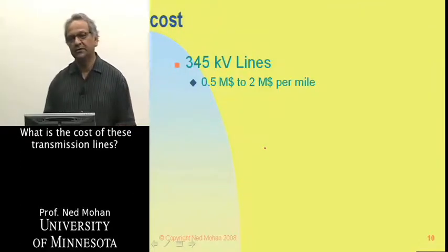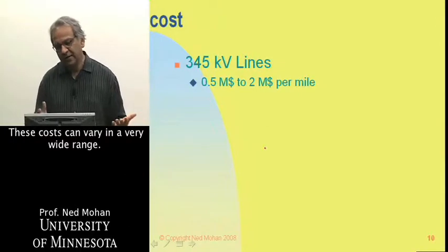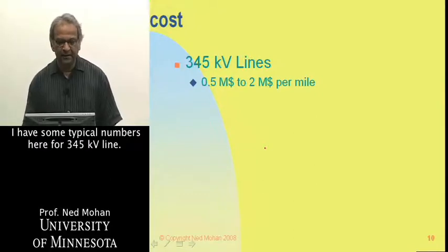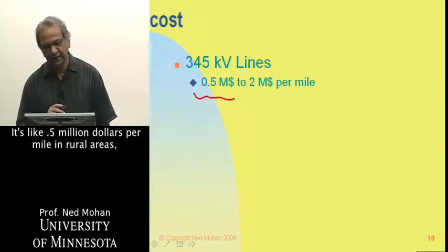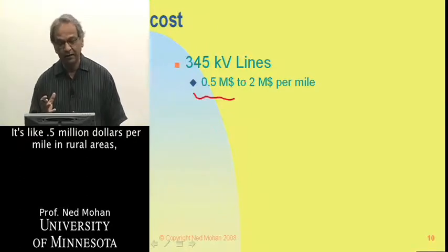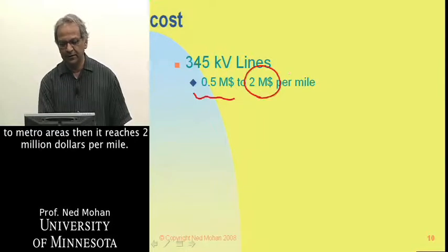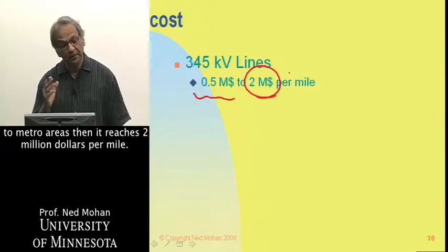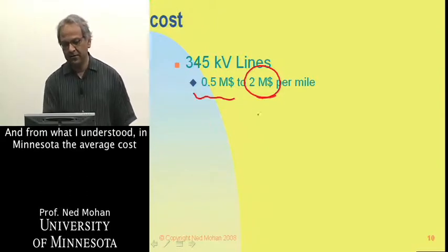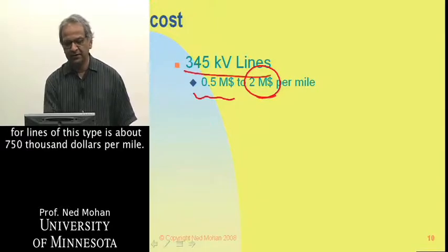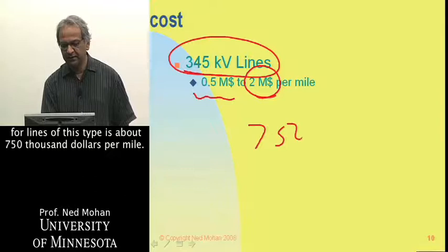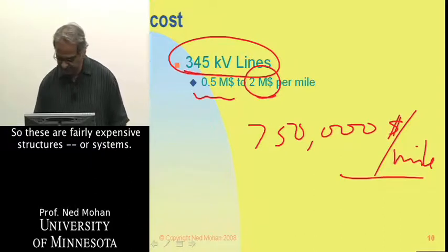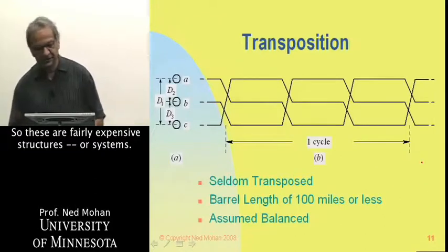What is the cost of these transmission lines? These costs can vary over a wide range. For a 345 kV line, it's about $0.5 million per mile in rural areas, but closer to metro areas it can reach $2 million per mile. In Minnesota, the average cost for lines of this type is about $750,000 per mile. So these are fairly expensive systems.